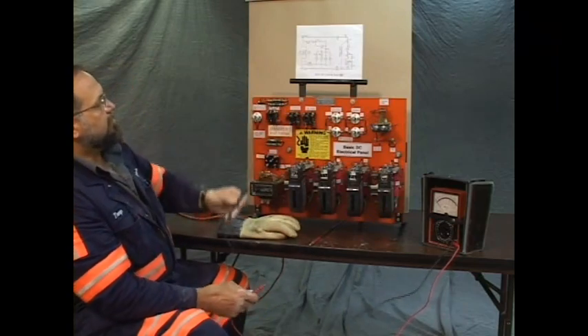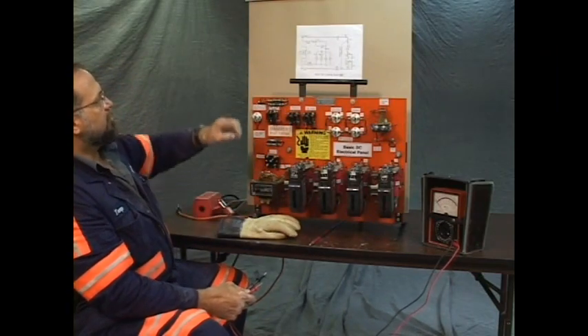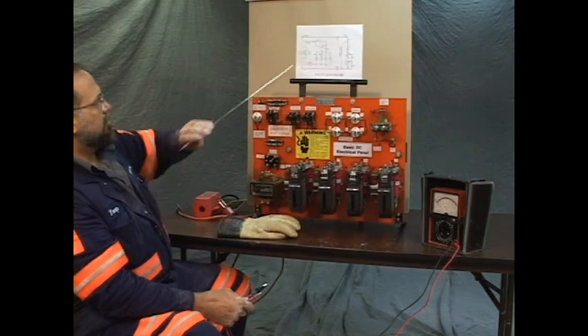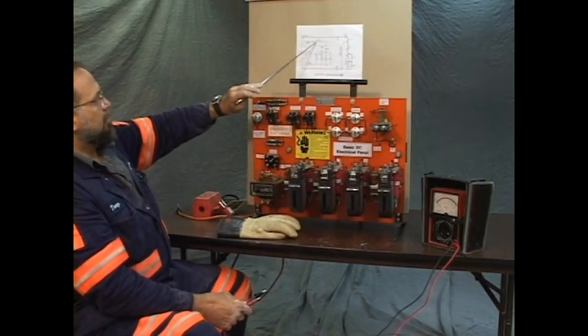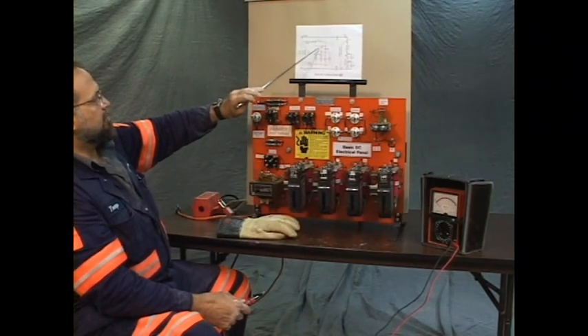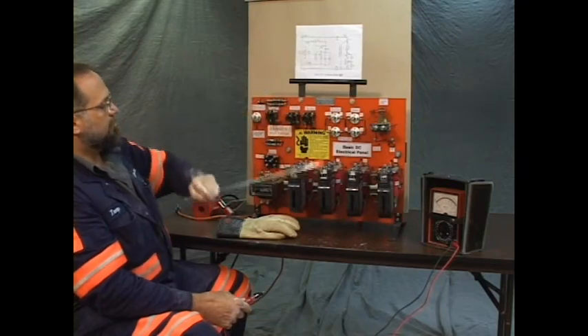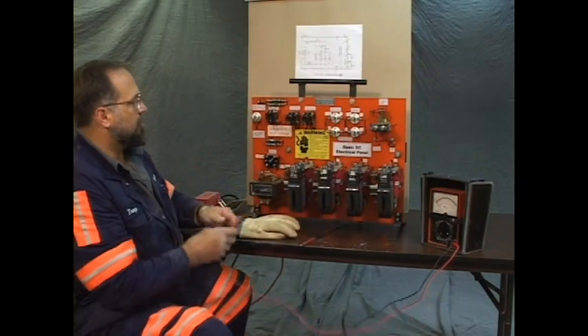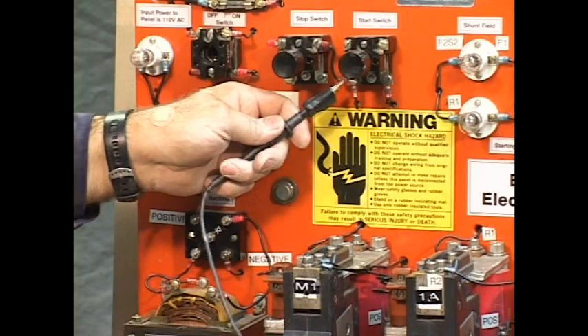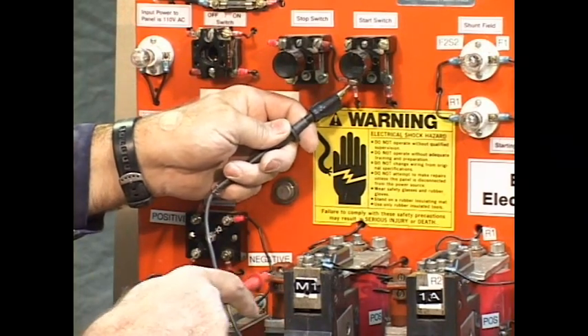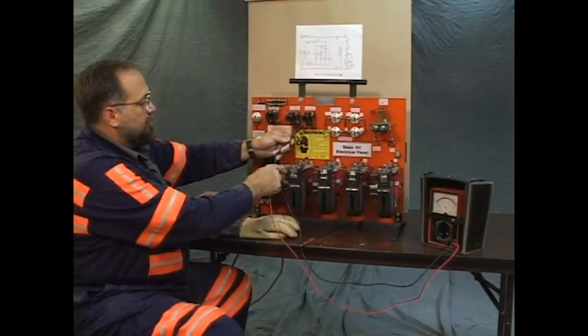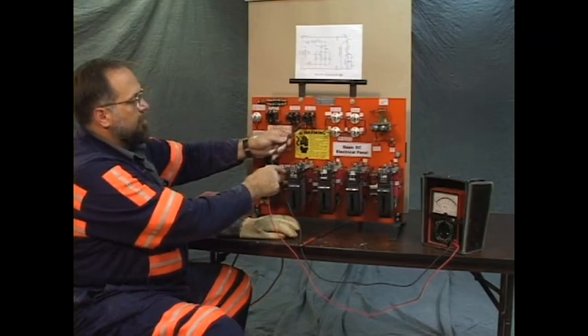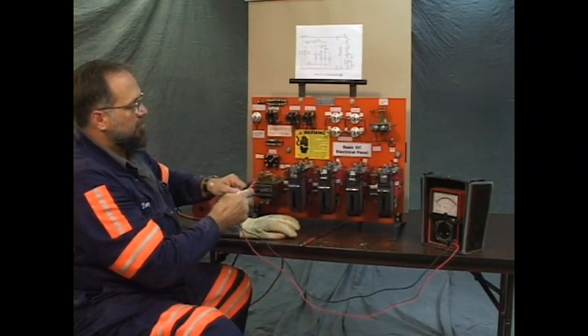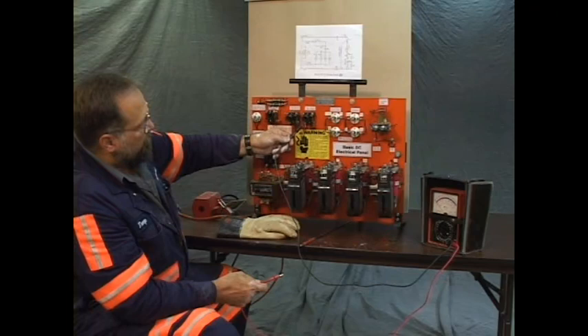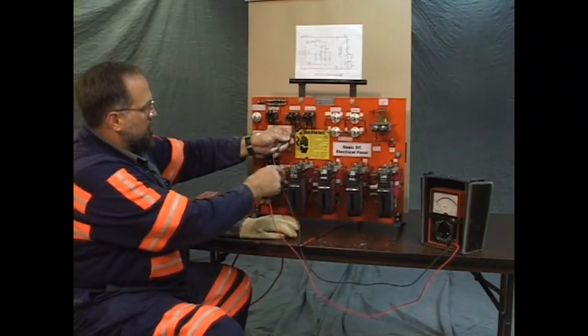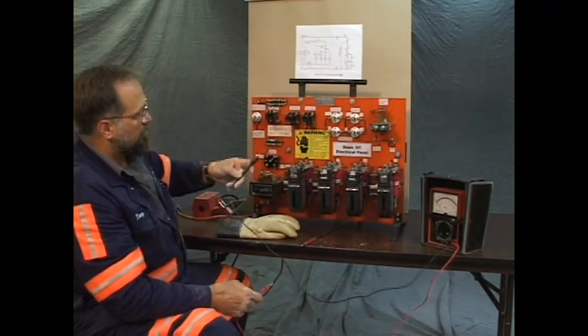The other part of the circuit that's involved here is wire. There's a wire that connects the line side of the start switch to the top of the mercury tube. We can test that wire for continuity. We should have a circuit there, and the meter indicates there is no circuit. We're going to test our meter just to be sure. And there is no circuit there.